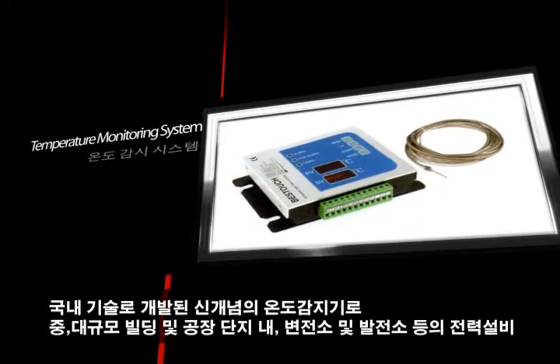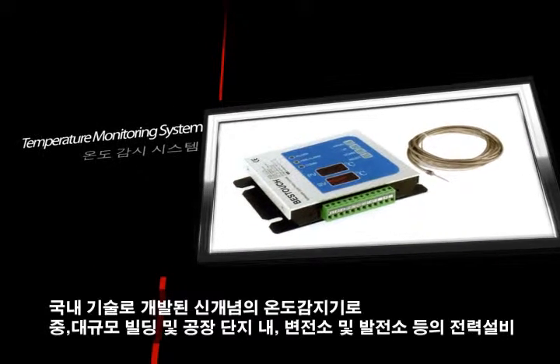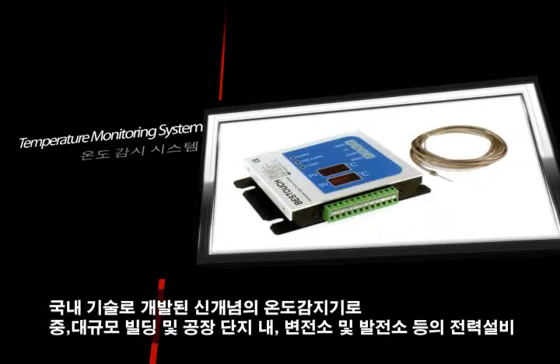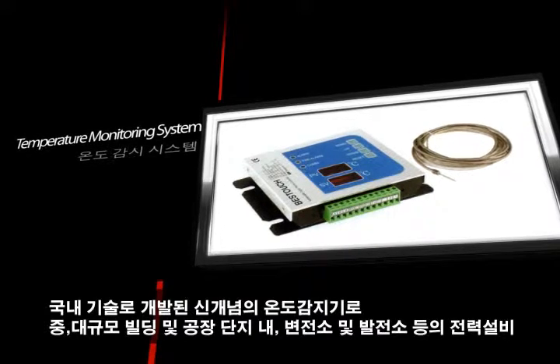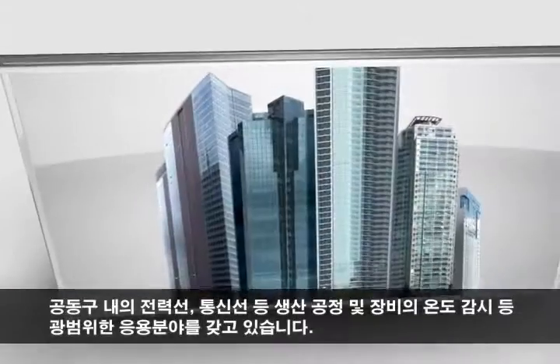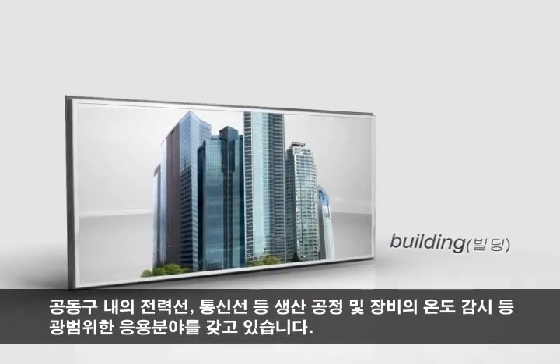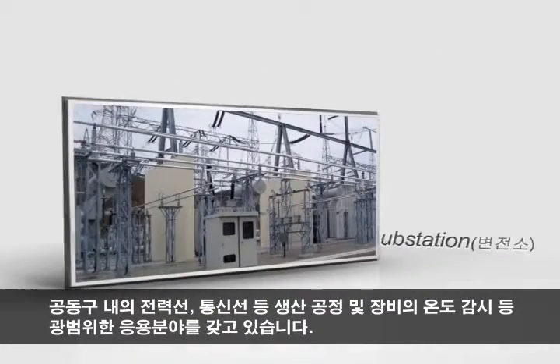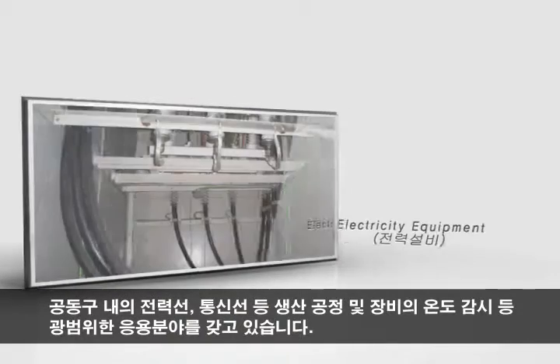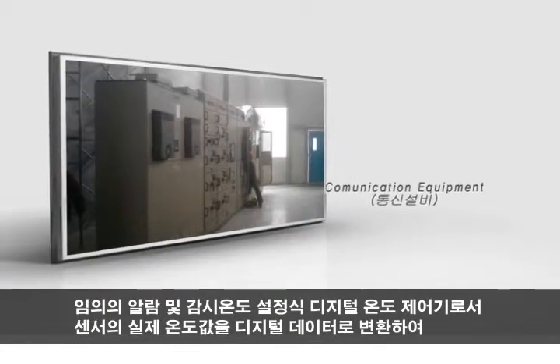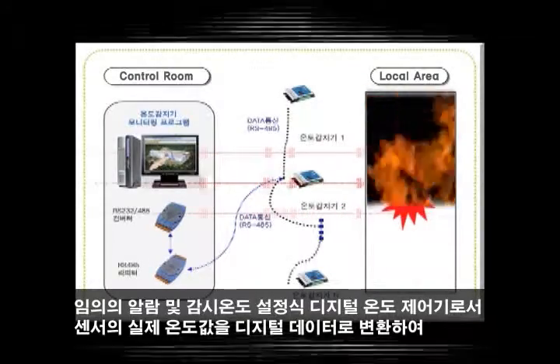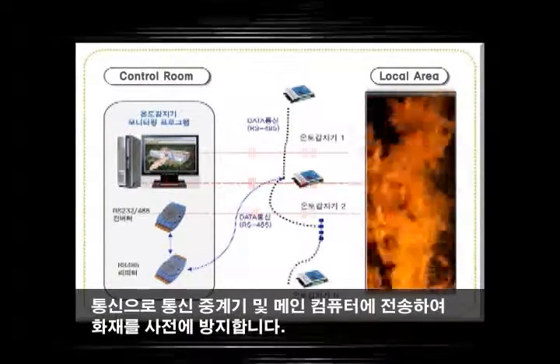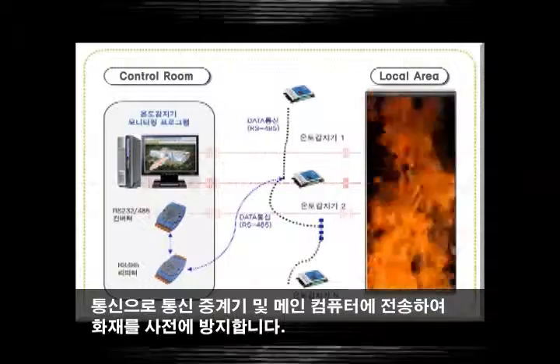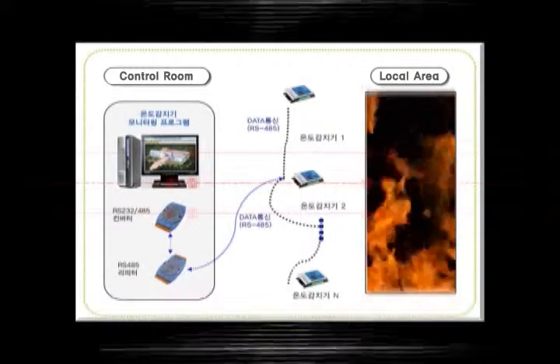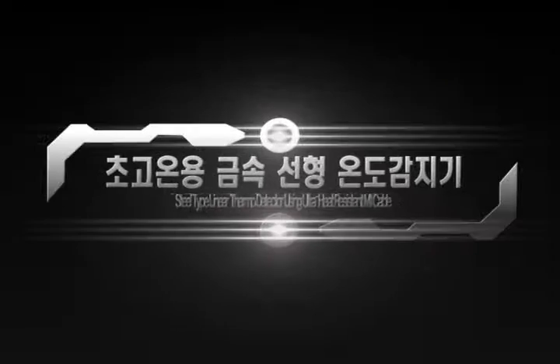This innovative temperature monitoring system was developed with domestic technology and is suitable for monitoring temperature in all power equipment, power lines, cables, etc., in mid to large buildings, factories, substations, and power stations. This system is a digital temperature controller with optional alarm. It prevents fire by collecting the value of actual temperature, converting it to digital data, and transmitting the data to the main system.